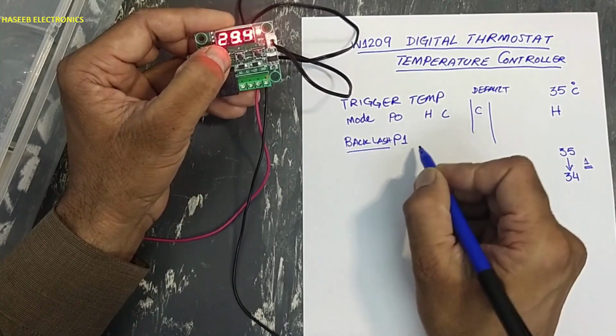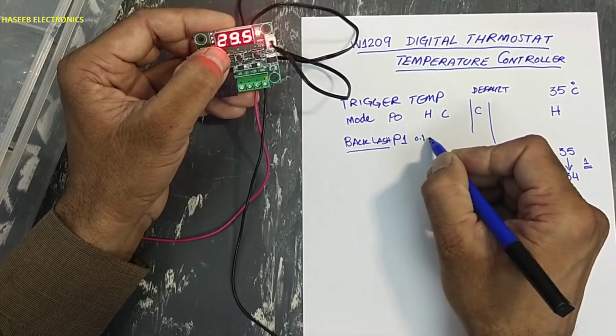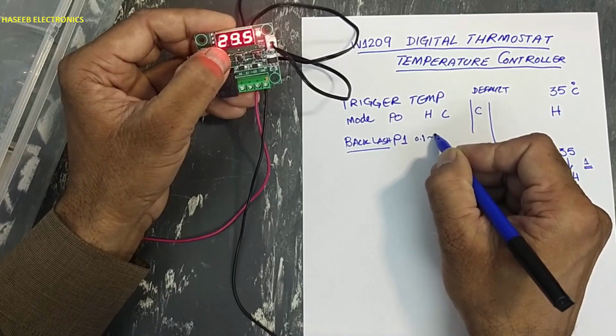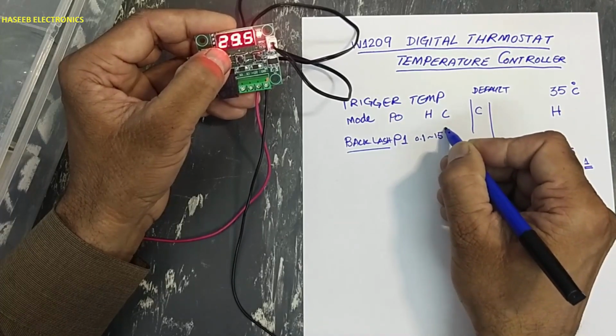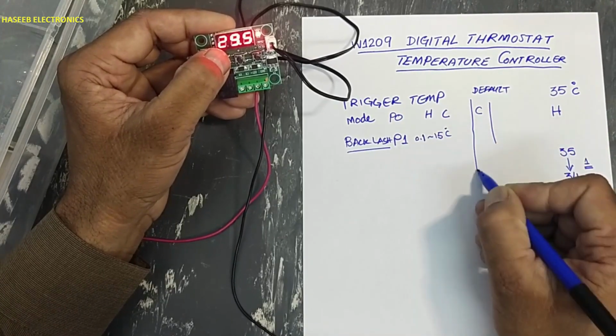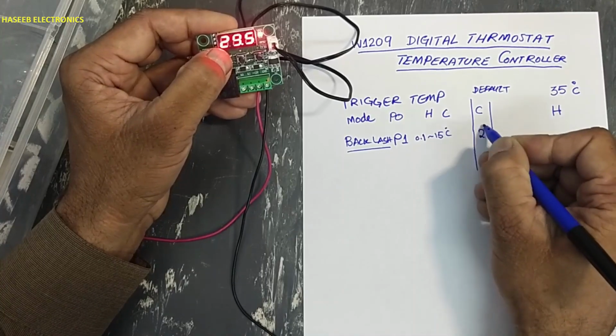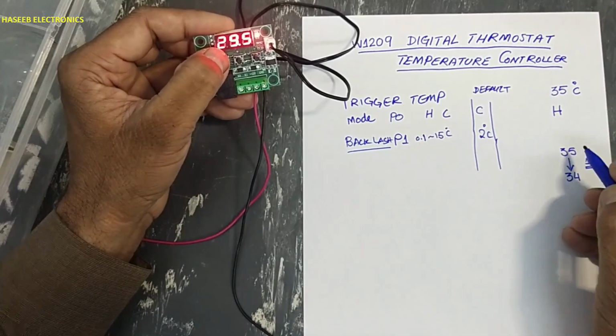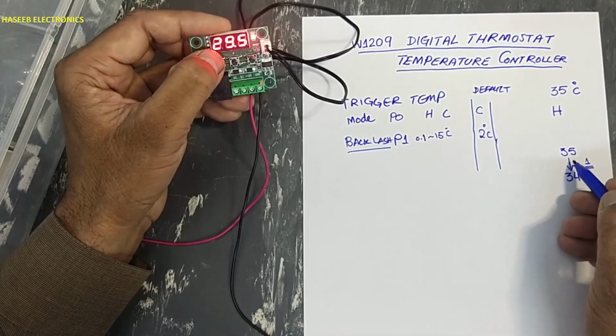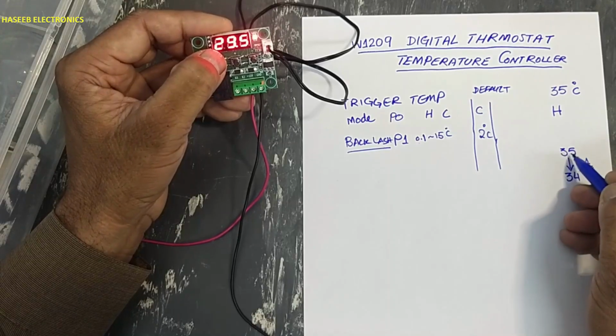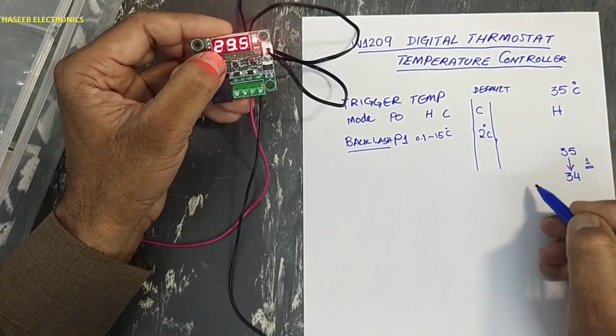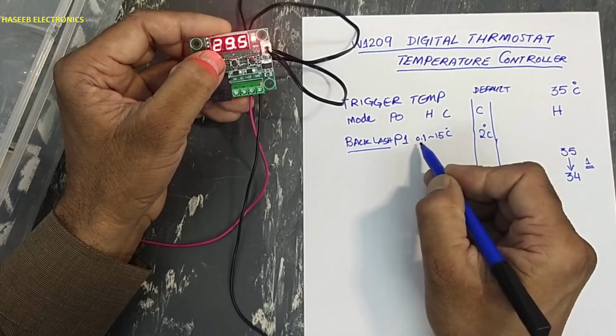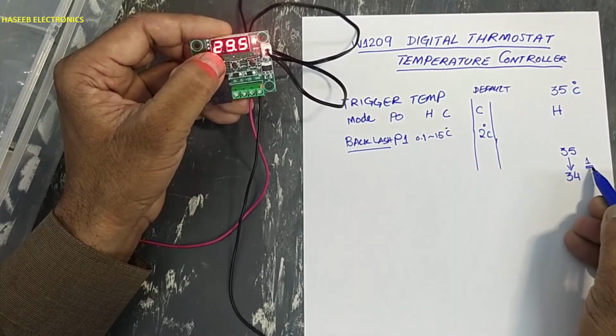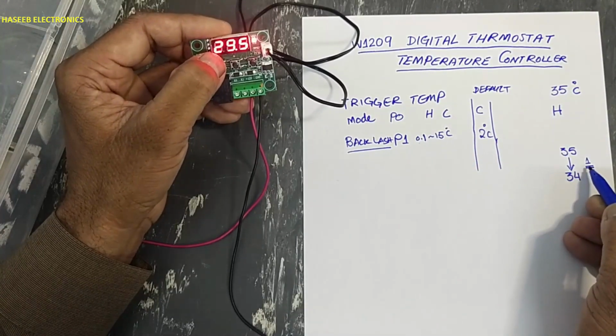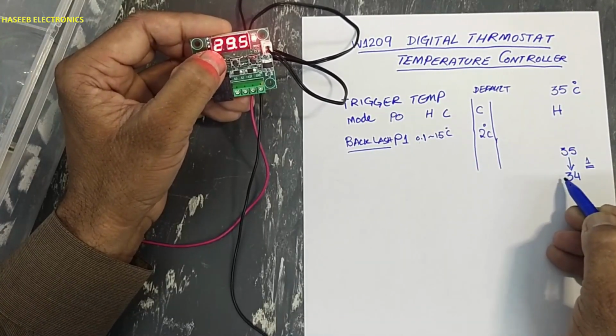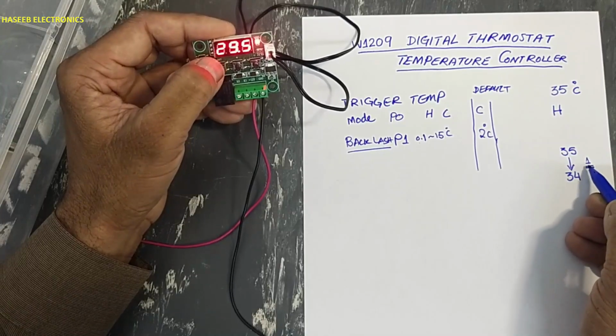In P1 mode, we can set from 0.1 degrees to 15 degrees. The default setting is 2 degrees. If we set 0.1, it will maintain the temperature between 35 and 34.9, because it is 35 minus the backlash temperature. If we want to set it between 35 and 34, we will set 1 degree.